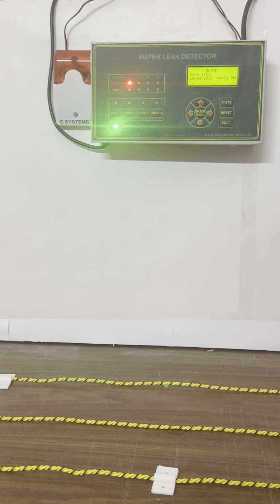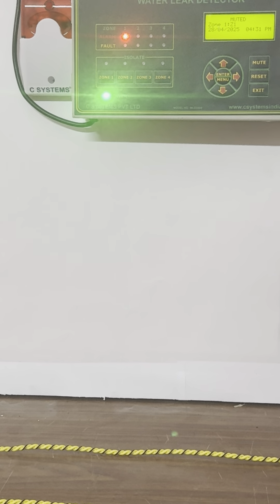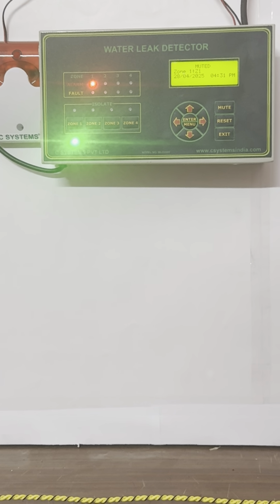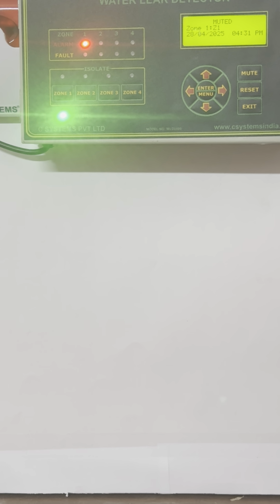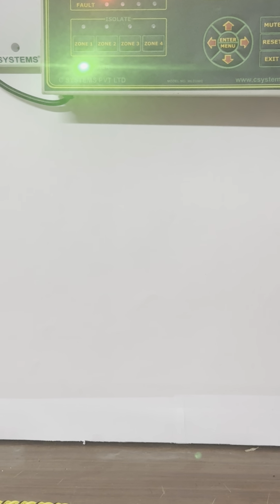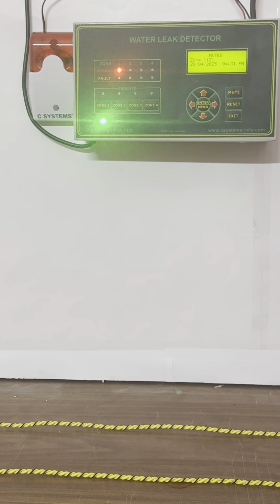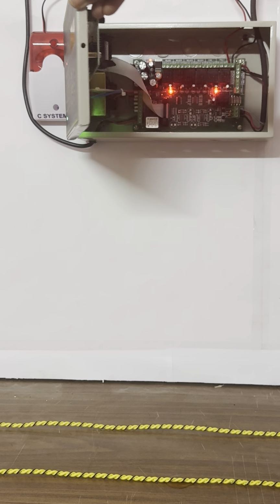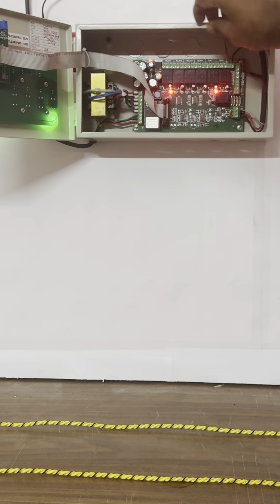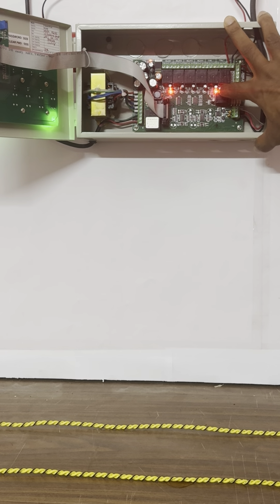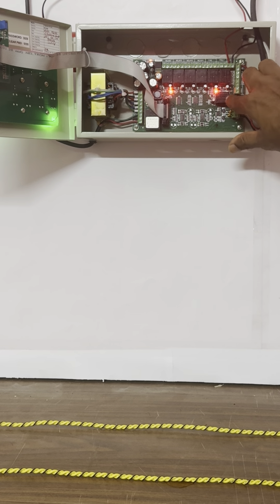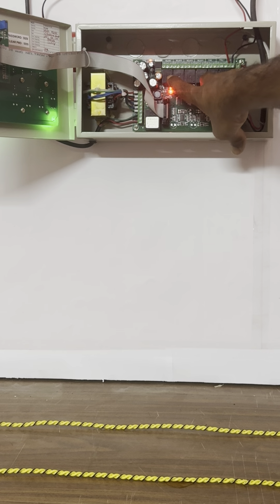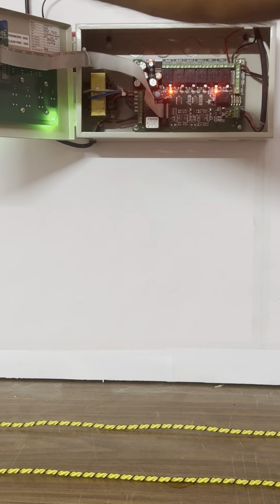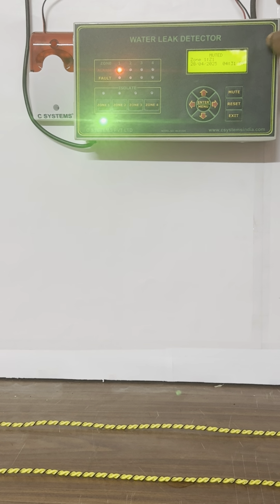As you could see, the zone 1 LED is activated, and you will be able to see the display showing mute because I have pressed the mute. After the mute is pressed, the same indication is available in the output. You can see in the output the hooter output as activated. The fire output is activated, the hooter is already activated and we have muted it, and relay 1 is also activated, the corresponding LED is also activated. So this is in alarm condition, but we have only muted the particular alarm.